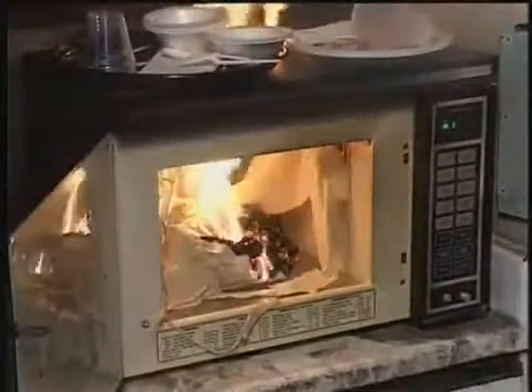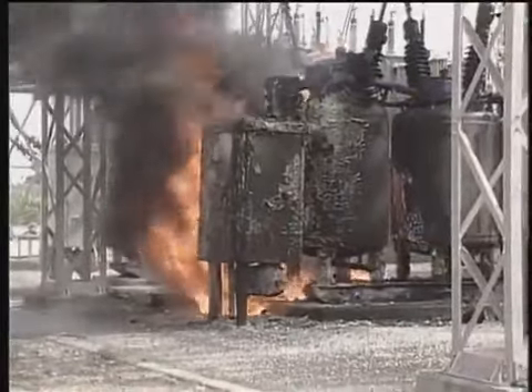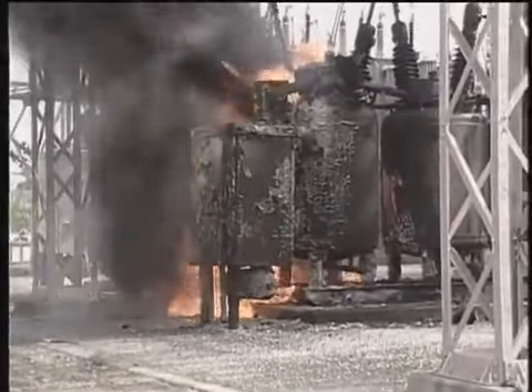When fires are caused by or involve electricity, the materials and equipment which are burning come under the Class C heading. Cables, wires, motors, machinery, anything which is energized, that is, which has power running through it and continues to be the heat source, results in a Class C fire. The safest way to extinguish the fire is to de-energize the circuit.